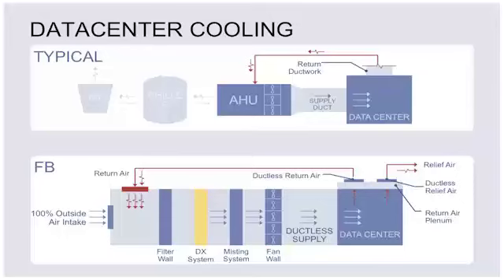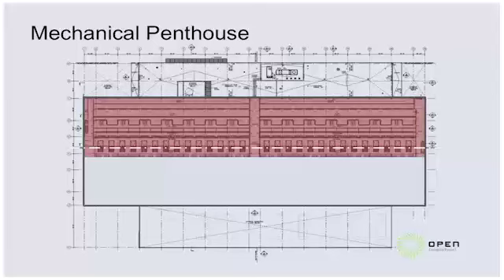So in a typical data center, we've got our cooling towers, we've got our chillers, and our prerequisite air handlers. What we've done is essentially eliminated two high energy usage components, just relying strictly on outside air. And again, as I mentioned, taking return air to warm up the air when it's too cold outside. You see the gold section here. When we designed our penthouse, we did a galley, which would allow us to add condensing coils or chilled water coils in the event that we do need to go full recirc in the future.